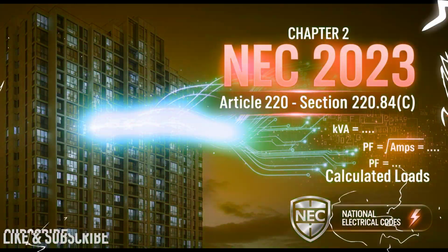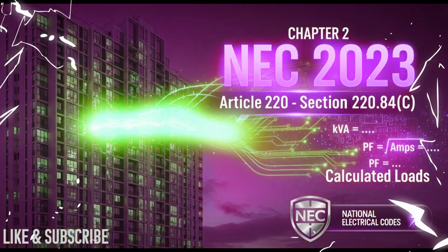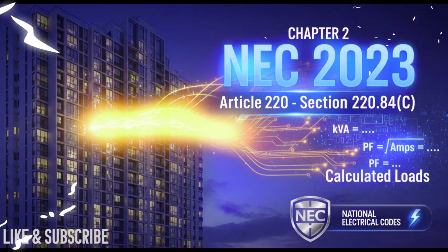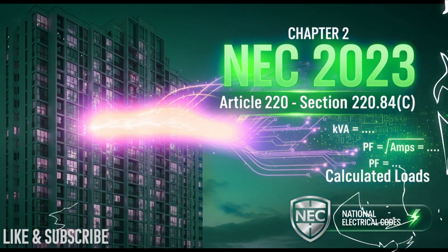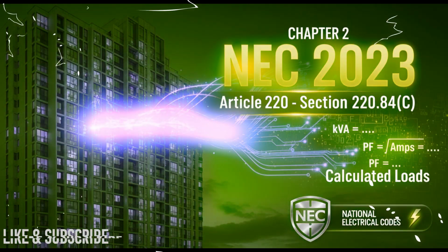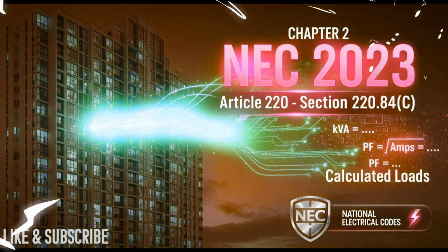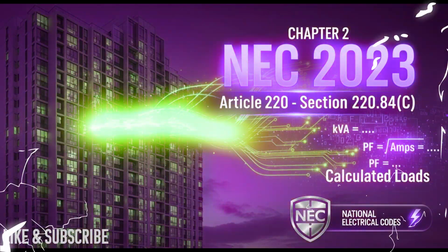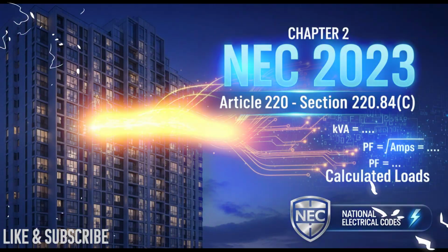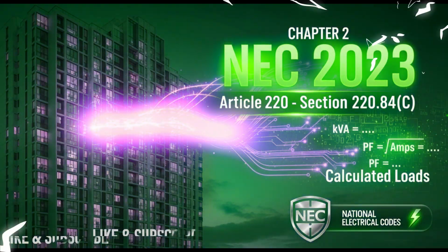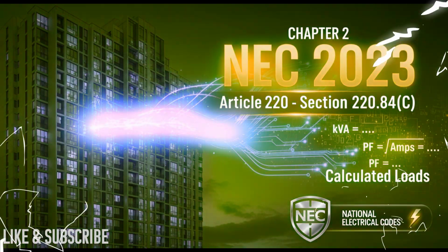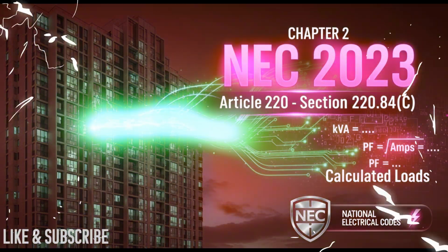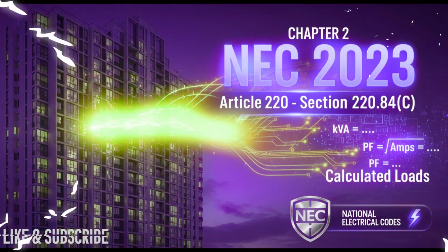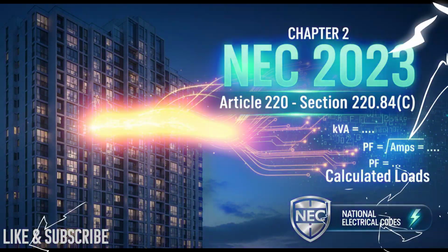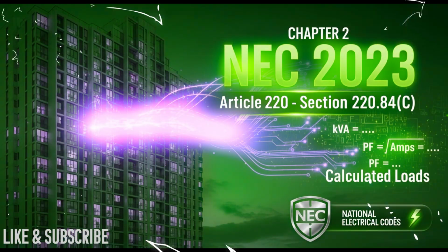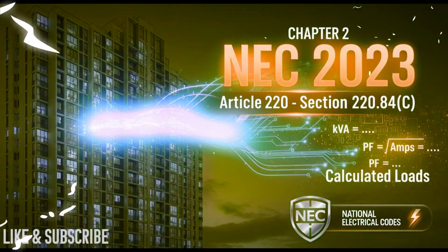What's next? Input 3. Input 3 is the fixed appliance group. Now, this is where the specific equipment choices for the building really start to matter, because this part relies on the nameplate rating. Nameplate rating? Yeah. What's actually stamped on the appliance by the manufacturer. Exactly, the official rating. The code is very clear. The designer must include the nameplate VA or wattage rating for a specific list of items. Okay, what's on that list? It includes all appliances that are fastened in place, things like garbage disposals, maybe hardwired dishwashers. Ceiling fans, too? Yeah. Anything permanently connected or located on a specific circuit that's not covered elsewhere.